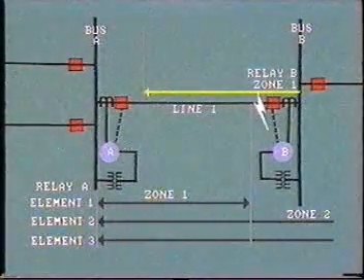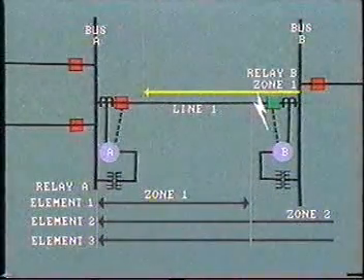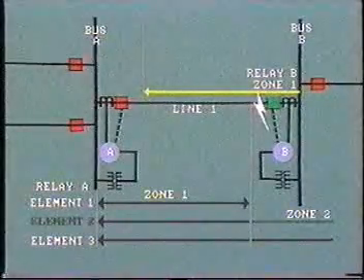Now, for a fault in the last 10% of line one, breaker B trips instantaneously, but we would have to wait for zone two clearing at A.